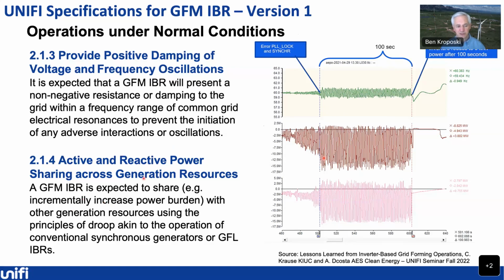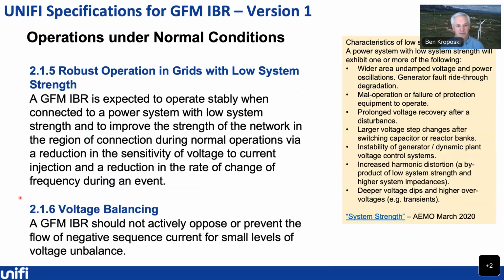We also want these devices to do real and reactive power sharing across a variety of generation sources. So when they're all working together, they can share the power load from the system. And then a couple more things under normal operating conditions. We want them to have very robust operations under low system strength, or a weak grid. People may not be that familiar with that term. I threw in a little bit of information over here on the side from the Australian system operator, AEMO, where they publish what they mean when they're talking about system strength. But in general, what that refers to is when you have changes in the system, how the other devices react to that.